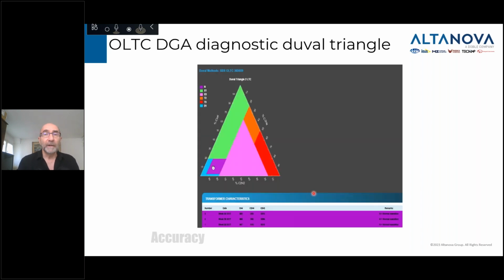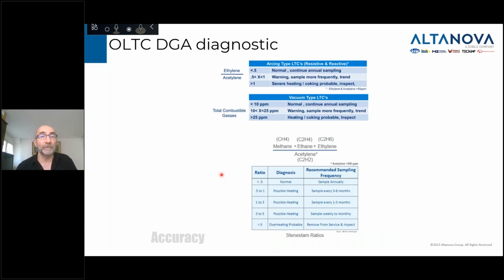Another one that's not being used broadly, but people are starting to do it, is a diagnostic tool for OLTC. Here you see an example of the Duval triangle used for specific customers who regularly measure DGA on their OLTC and put that data into the tool. Here you can see what it tells: mostly that you have a normal operation of that OLTC. Now, this is the Duval triangle for OLTCs. There are also other OLTC diagnostic tools that have been designed. You can see two of them, one being the Stenestam ratio. There are also other diagnostic tools being used internally.